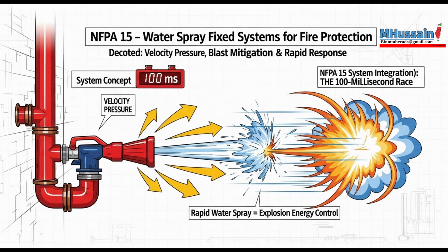Okay, so materials and joints are solid. Now, structural support. For big pipes, NFPA 15 gets incredibly specific in Table 6.3.2.2.2, detailing maximum heights for pipe stands based on pipe diameter and support arm length. Why such fine detail on a simple stand? It comes back to those dynamic loads. When a deluge system fires, you go from zero pressure to potentially hundreds of psi almost instantly. That creates shock waves, thrust loads. If the pipe stands are too tall, they can be too flexible, or they might even buckle. So the tables ensure rigidity.